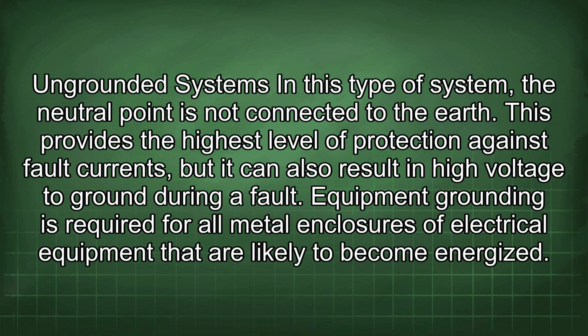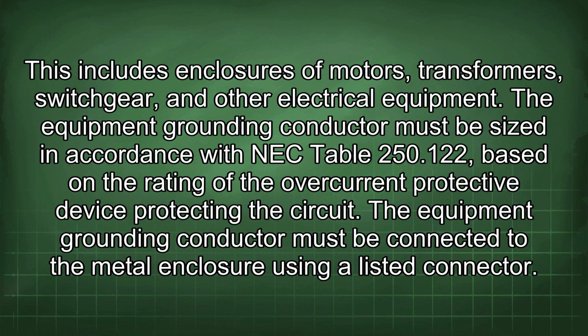Ungrounded systems: in this type of system, the neutral point is not connected to the earth. This provides the highest level of protection against fault currents, but it can also result in high voltage to ground during a fault. Equipment grounding is required for all metal enclosures of electrical equipment that are likely to become energized. This includes enclosures of motors, transformers, switchgear, and other electrical equipment. The equipment grounding conductor must be sized in accordance with NEC Table 250.122, based on the rating of the overcurrent protective device protecting the circuit. The equipment grounding conductor must be connected to the metal enclosure using a listed connector.